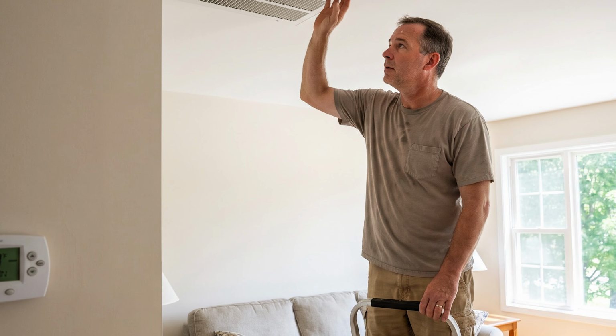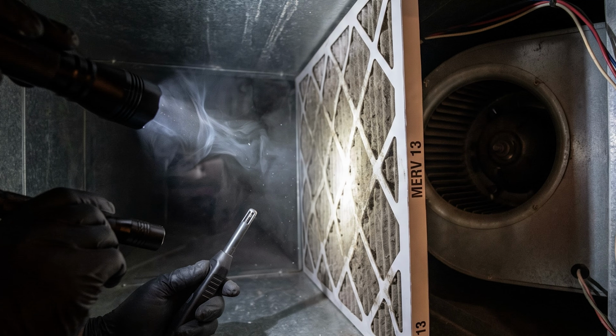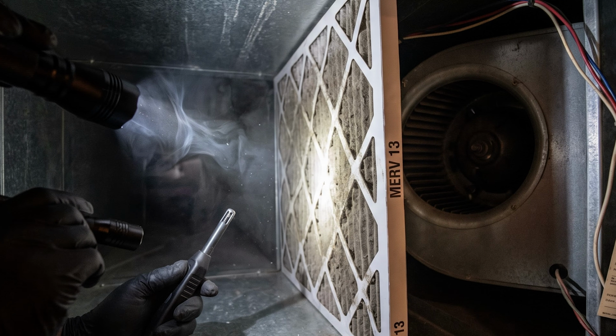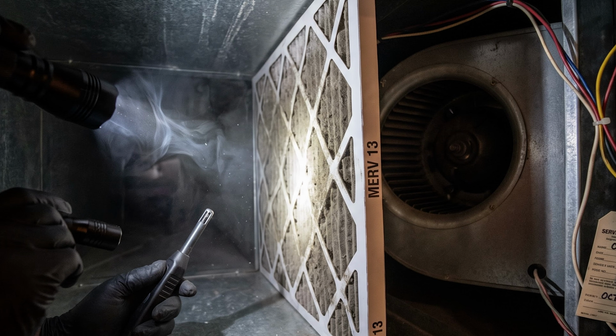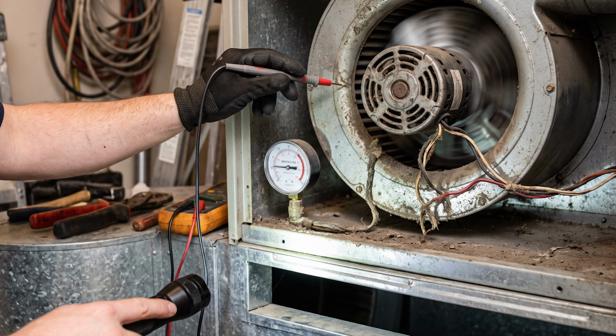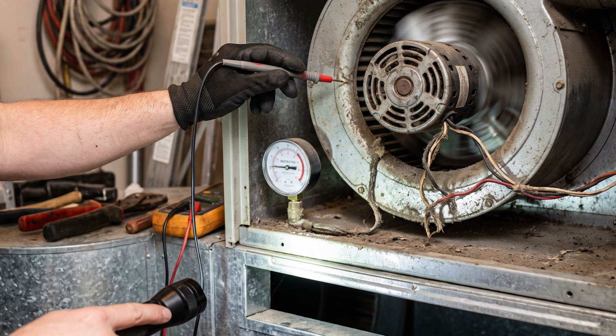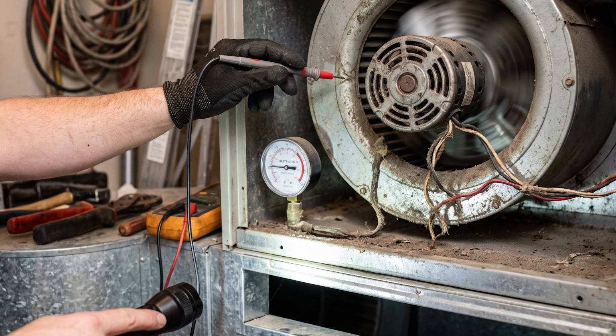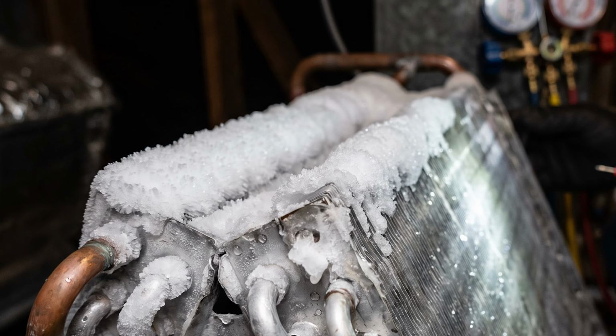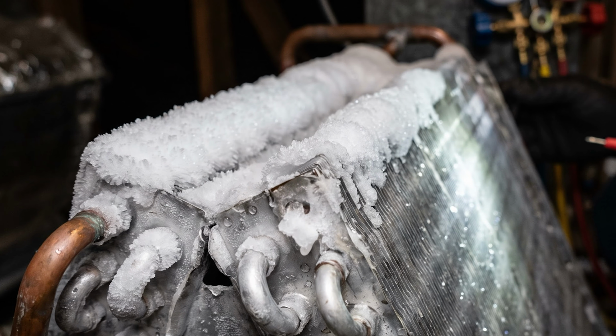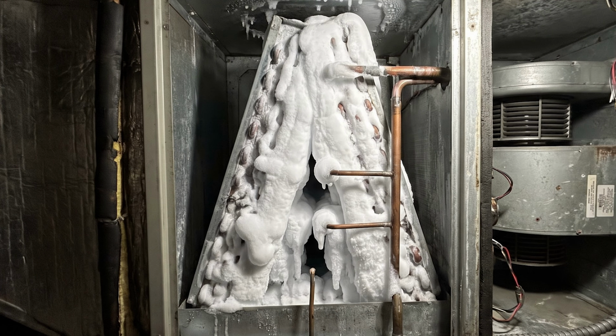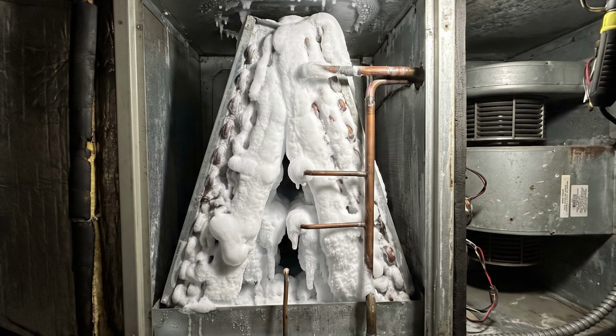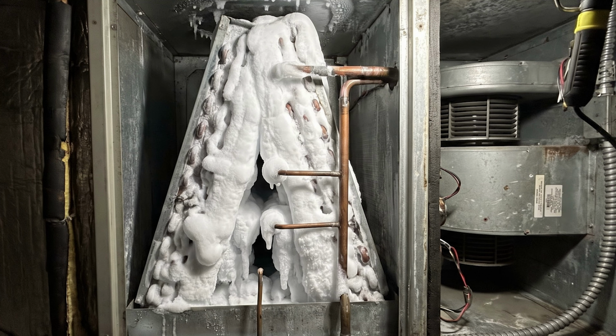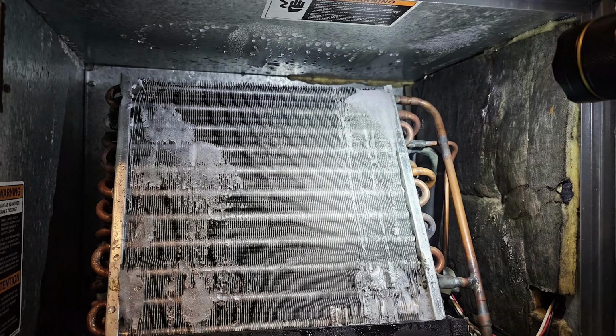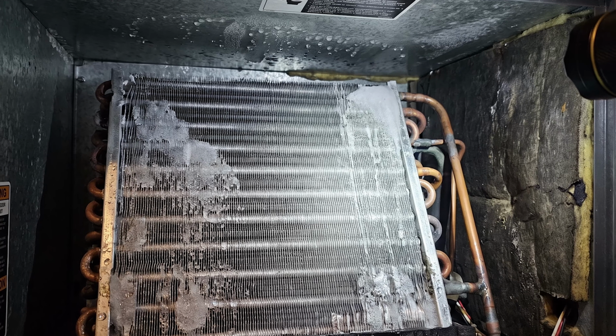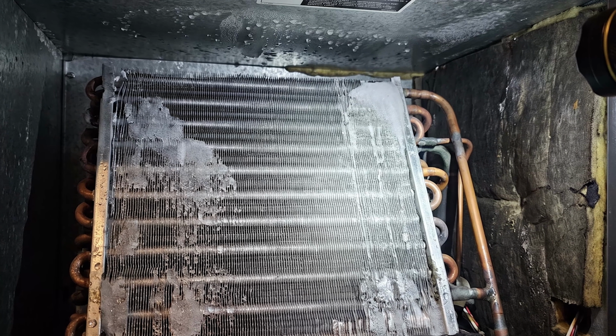When you restrict that airflow with a thick filter, 2 terrible things happen. First, the blower motor has to work much harder to pull air through the dense material. It overheats, uses more electricity, and eventually burns out completely. Replacing a blower motor can easily cost $800. Second, without enough warm air moving over the indoor coils, the system gets too cold. The condensation on the coils literally freezes into a solid block of ice. Once the coil freezes, no air can pass through at all. Your system will run continuously, blowing absolutely nothing, until the compressor outside finally gives up and dies.